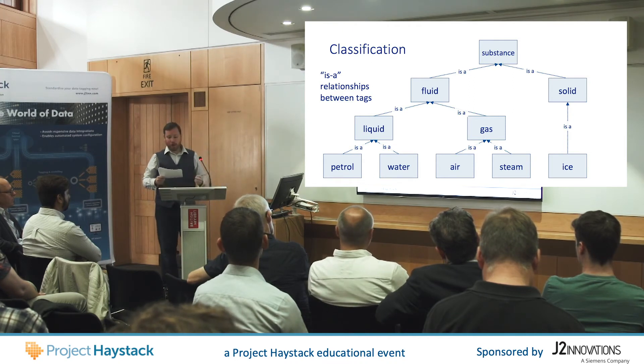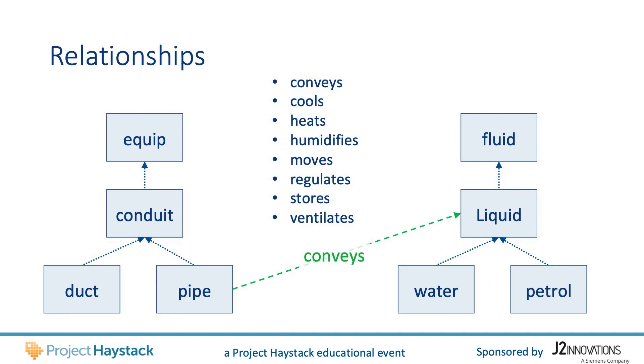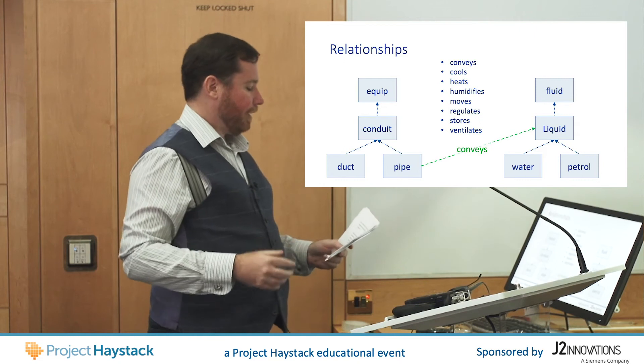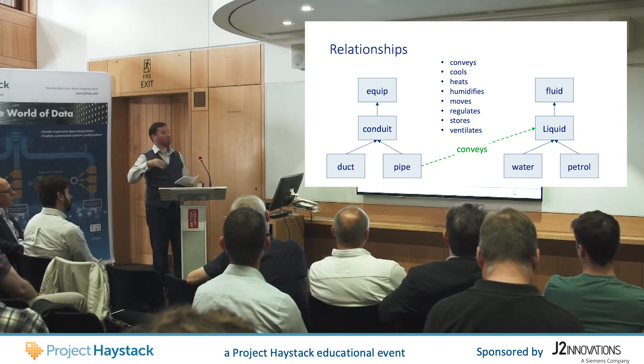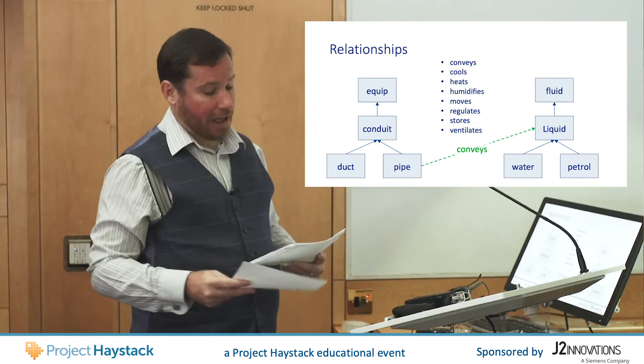These hierarchies are an example of an ISA relationship, but Project Haystack 4 goes further. Version 4 gives us a mechanism to describe other relationships between tags and hierarchies. Here we define that a pipe conveys liquid or water. Note that Haystack gives us two things: both a mechanism to formally define these relationships and a standard library of building automation terms with those relationships already defined. These standard libraries include relationships such as cools, heats, regulates, and ventilates.